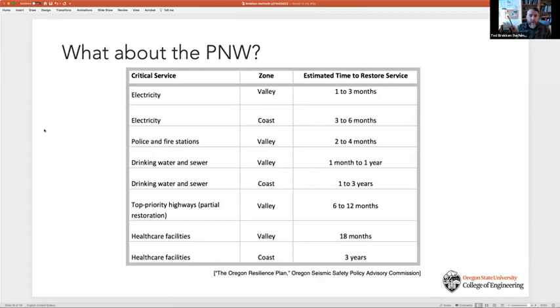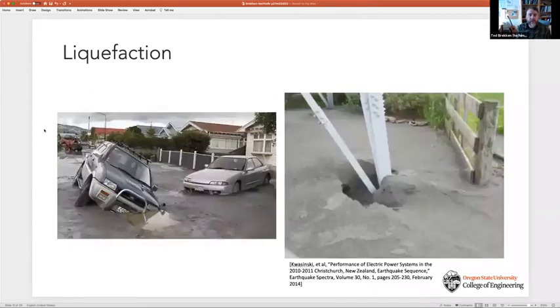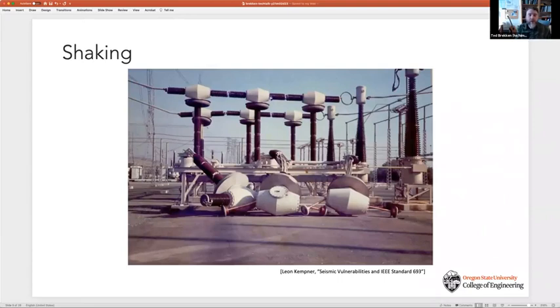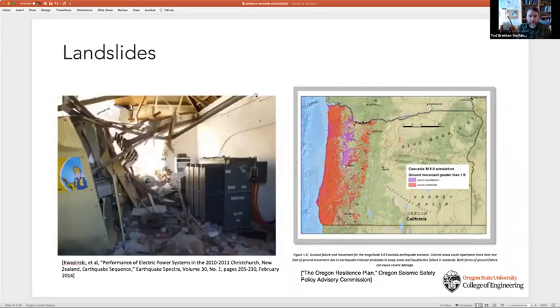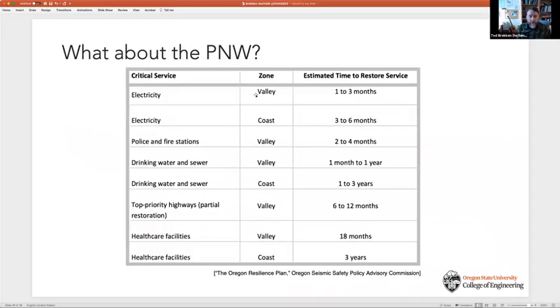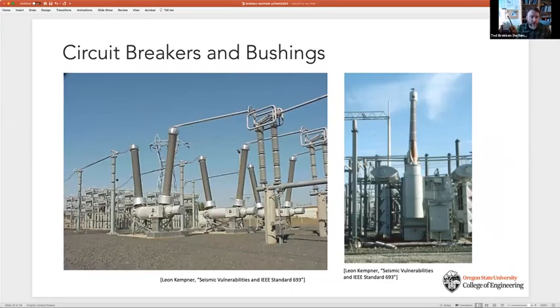One of them is what we call a live tank circuit breaker. This picture here shows a live tank circuit breaker, which tends to be very top heavy. It's an older circuit breaker style. In many cases they're being replaced by what's called a dead tank circuit breaker, where the structure is mostly on the ground, giving much better robustness properties. So some things are happening organically over time, like gradually moving from live tank to dead tank circuit breakers.